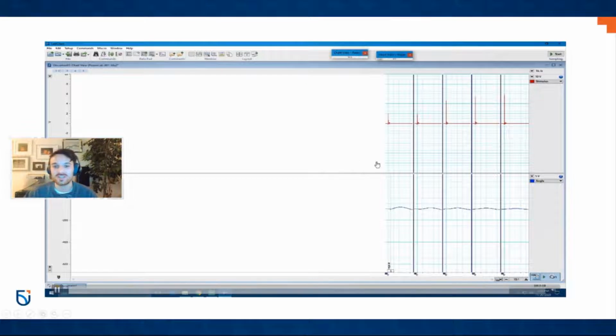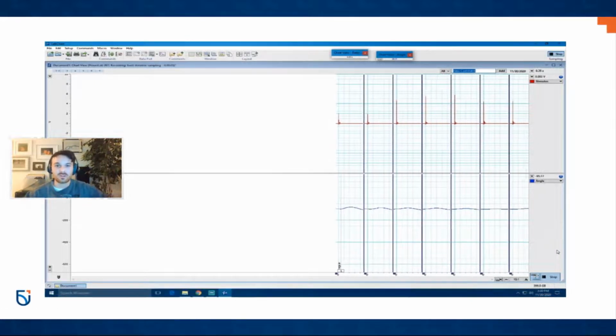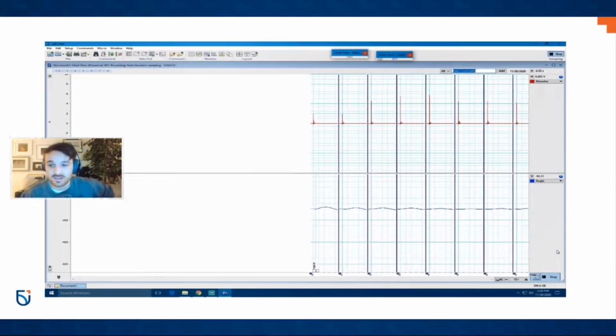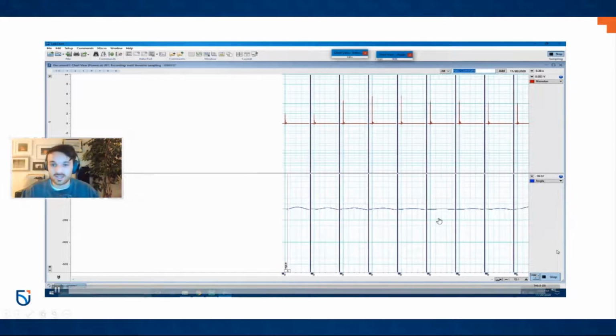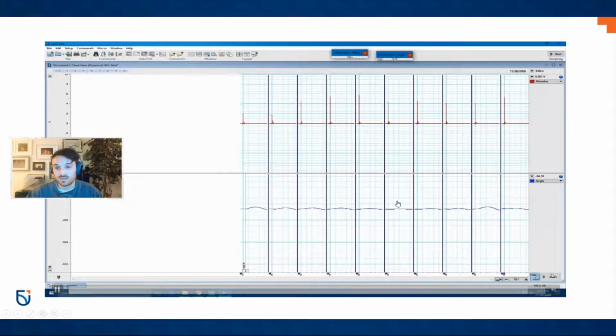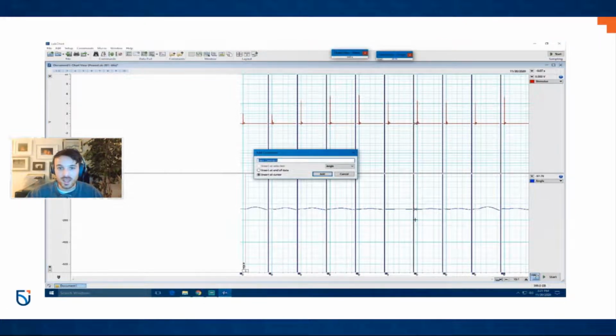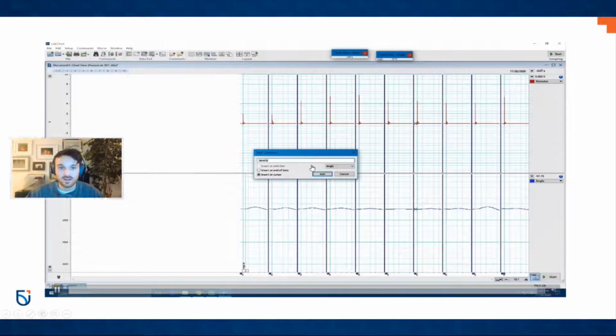Then making sure, again, once you've practiced that once, you're going to hit start. You're going to do it 5 more times, this time with the person performing that Valsalva maneuver the entire time. And once we collect all those, we'll make sure to comment which ones are Transducer, because we're going to need to know that for our analysis. So again, we count out our 5, add our comment by right-clicking, add comment, and type in Valsalva maneuver, whatever you want to type in.